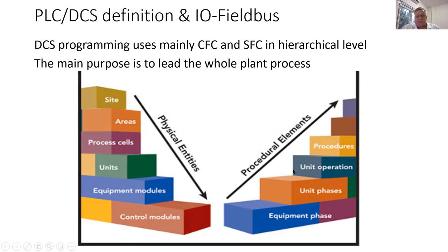And this is then the software side. So we have equipment phases, that means some sequences in an equipment module. They will be controlled from unit phases, which are also nothing else than sequences. So the unit phase gives different commands to different equipment, depending on what you want. Let's say a unit phase can handle a filling process and start the temperature control and weighing, and then do some transfer also. A unit operation is again just a higher level which calls unit phases. So that is like the sequence which I have shown shortly before, just steps and transitions from this level on up to the top.